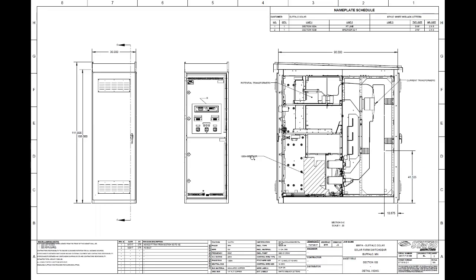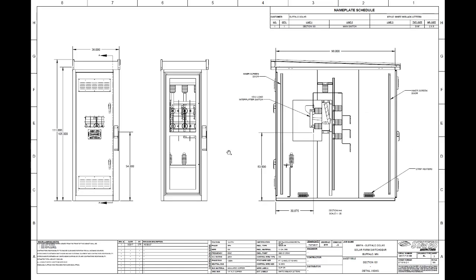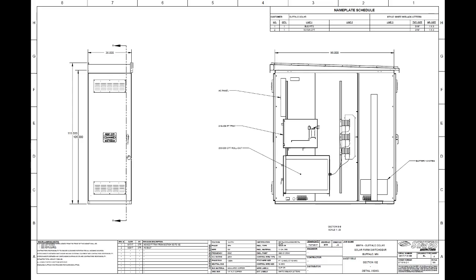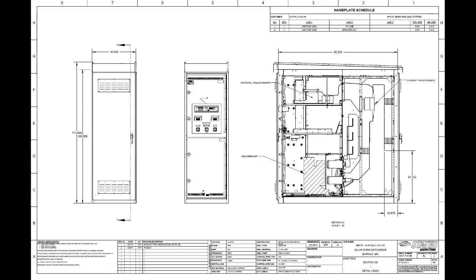Here, just highlight a couple of our different construction methods. This one was actually a medium voltage switch on one end of the installation. That was the actual utility disconnect. The utility required simply a load break visible disconnect switch. And the customer actually had a PT compartment, a CPT compartment, and then a draw-out circuit breaker is what the customer on this one wanted to actually be able to disconnect their system as well.